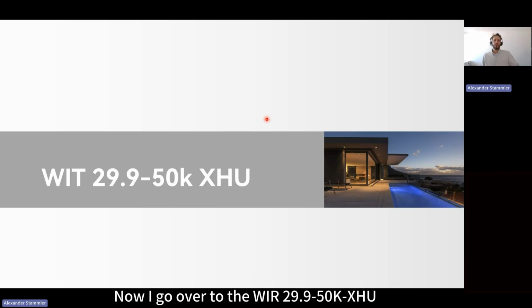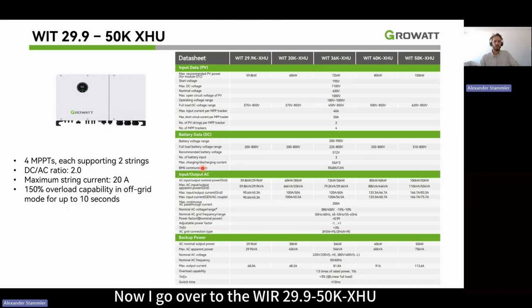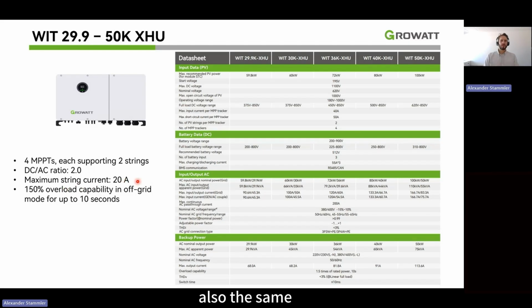Now I go over to the WIT 29.9 to 50K XHU. It has 4 MPPTs, each supporting 2 strings. It has also a DC-AC ratio of 2, similar to the other systems that I showed. Maximum string current of 20 ampere, also the same.